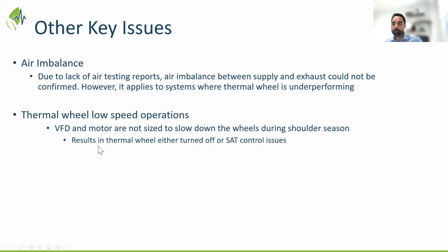Thermal wheel low speed operation is another issue, directly related to the operation of these units during the shoulder period and also control of the supply air temperature. These are huge wheels, and if the motors and the VFDs are not sized to run to the lowest RPM possible, then during the shoulder season these wheels cannot be used, because they deliver air that is either too warm or too cool, since they can only operate at a certain minimum RPM.